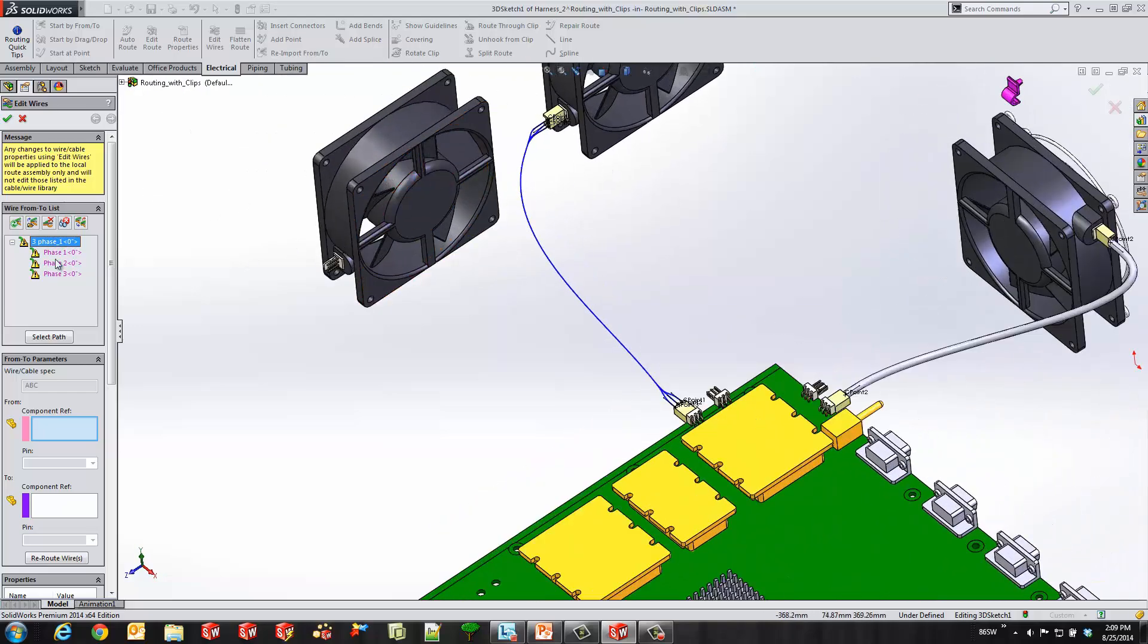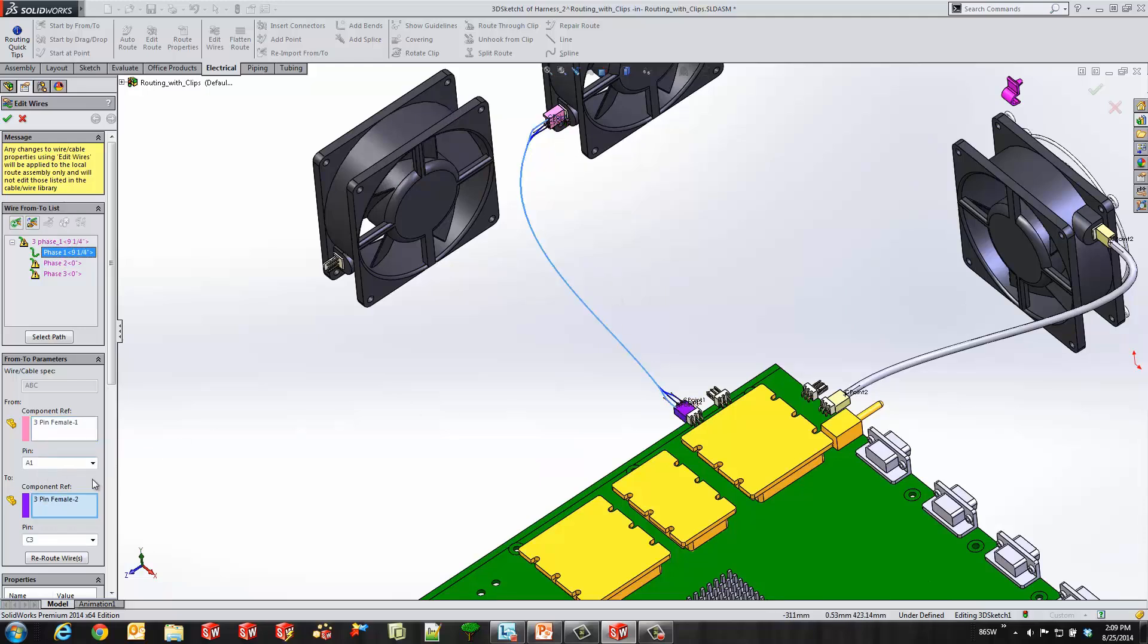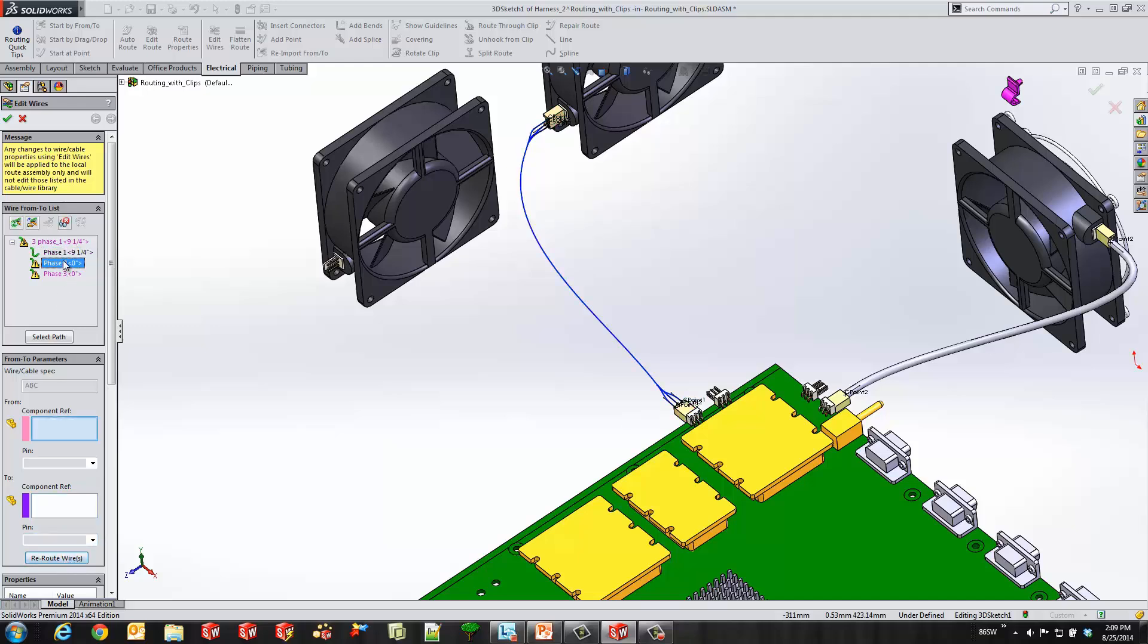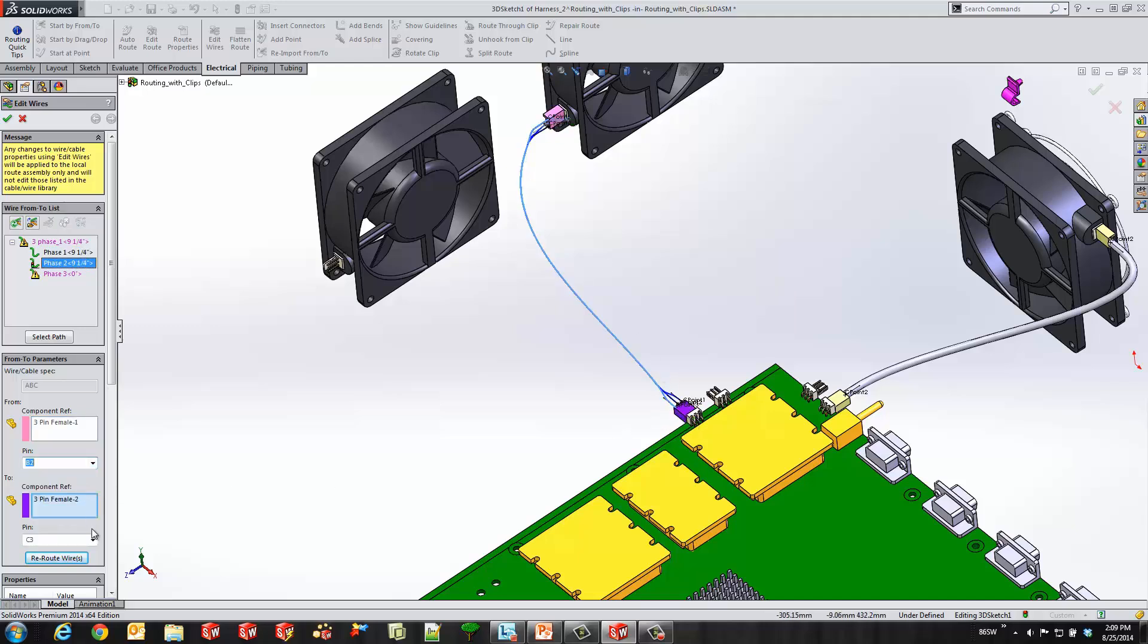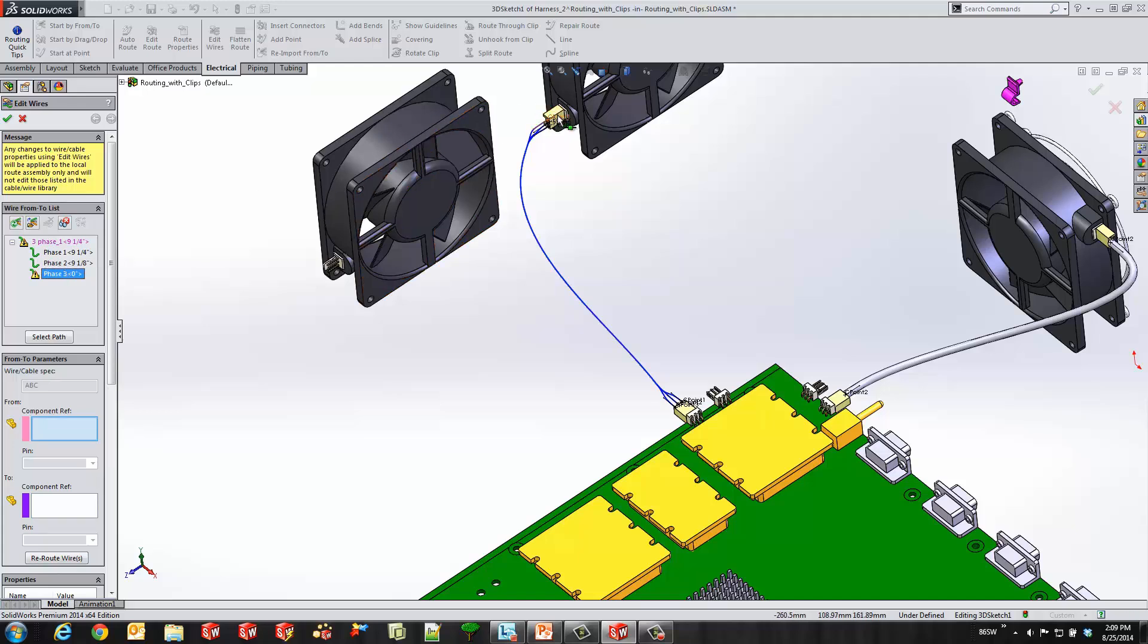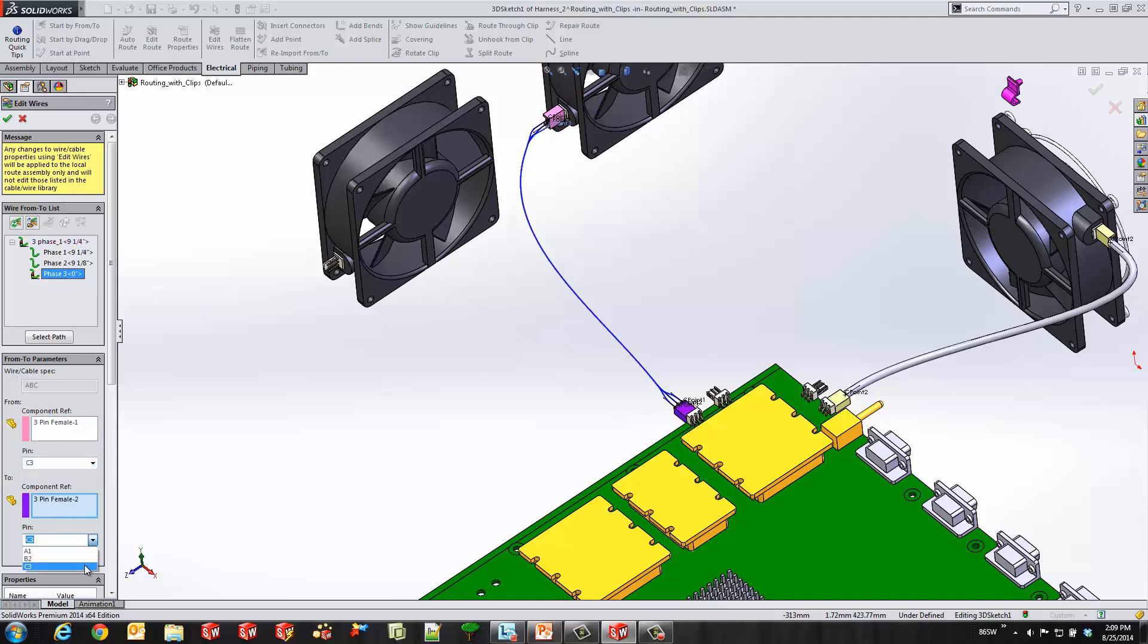I'm going to start off by selecting the first core phase one. Selecting the component, selecting the other component. And then now this is where I specify which pin that wire is going from. So A1 to A1. Remember to hit that reroute wires. And I'm going to do this a couple more times. So just change it to B2 and B2. And just remember after each time to hit that reroute wires so it routes that segment. And I'll do it one more time from here to here. And reroute from C3 to C3. And you'll see it has the links up here in the field. But we'll go ahead and look at that again when I get to the drawing.